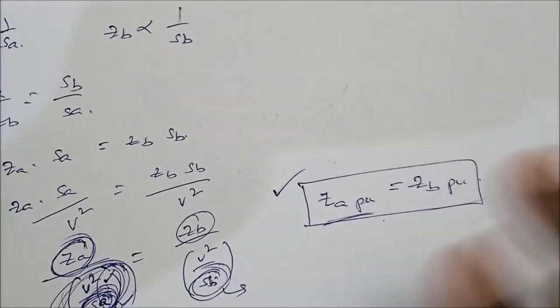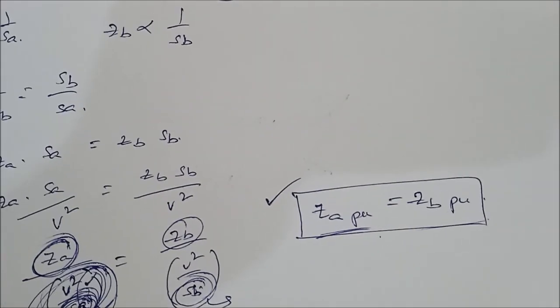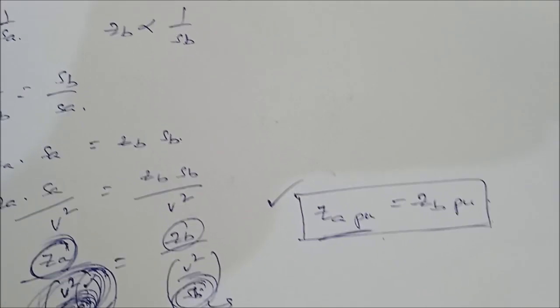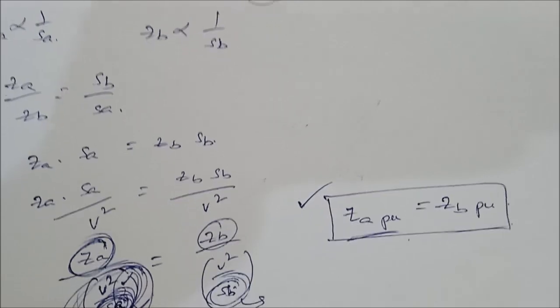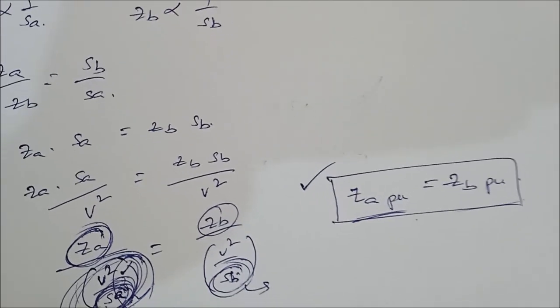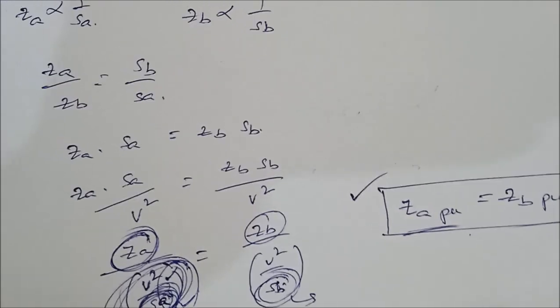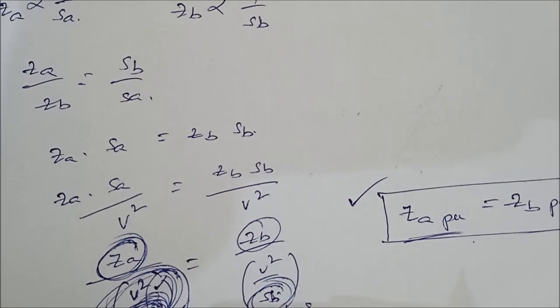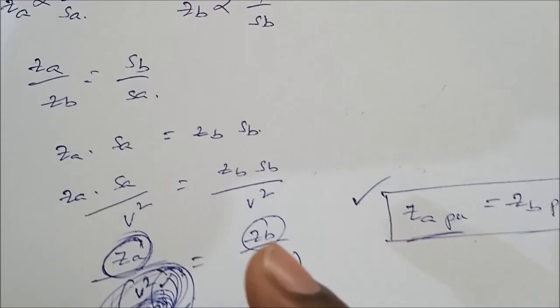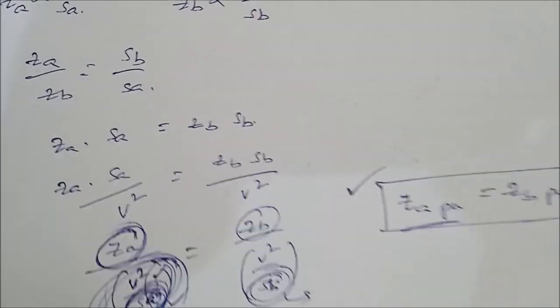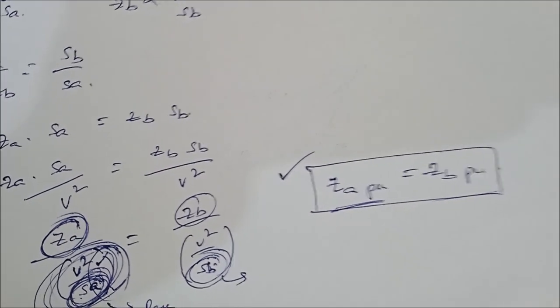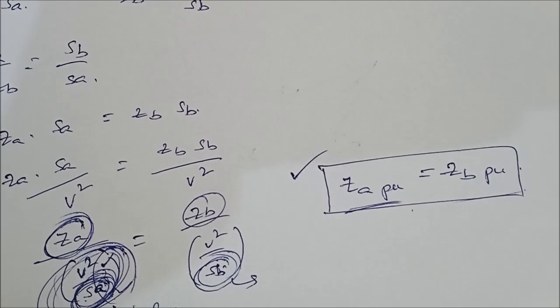This completes the concept of parallel operation of transformers. Regarding unequal voltage ratios: when Ea ≠ Eb, circulating currents are present in addition to the load currents — that is the key difference. In the cases discussed here, since Ea = Eb, there are no circulating currents. Thank you.